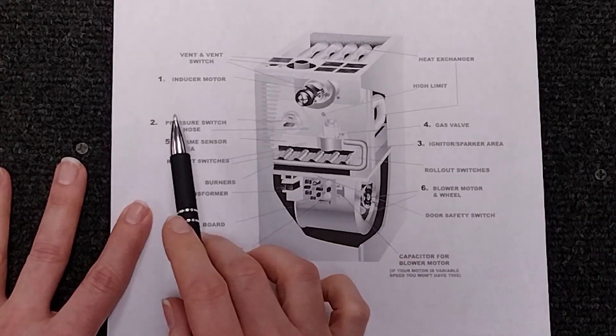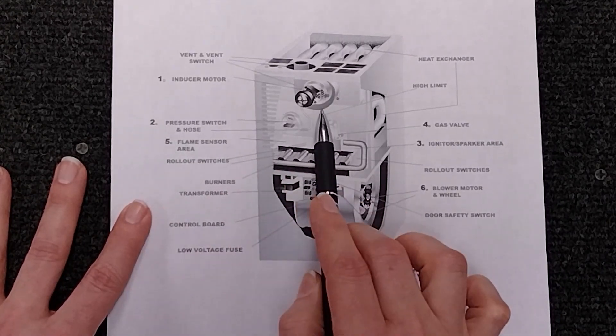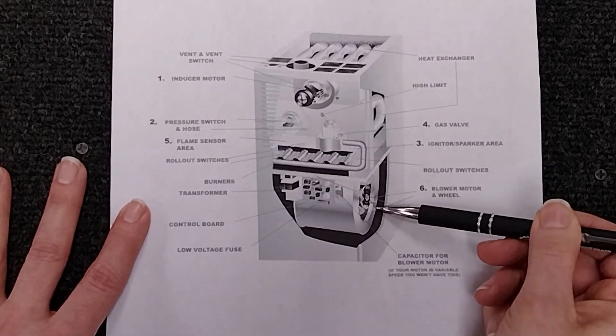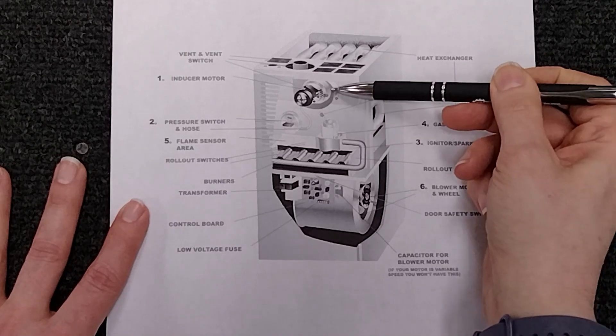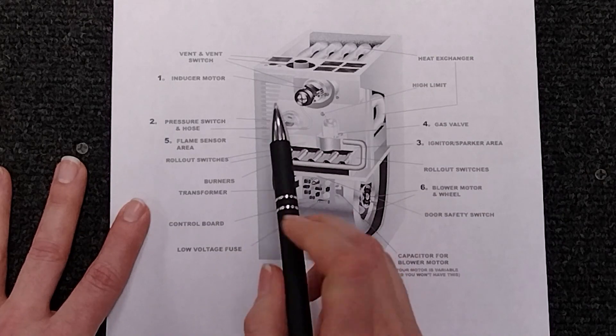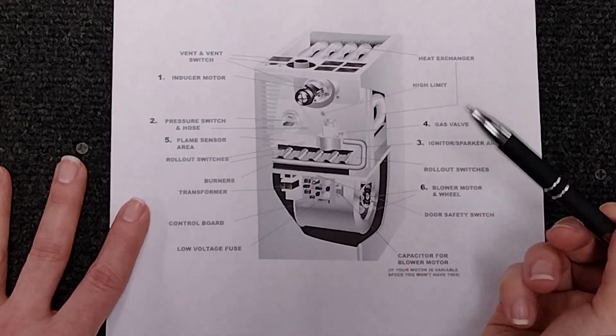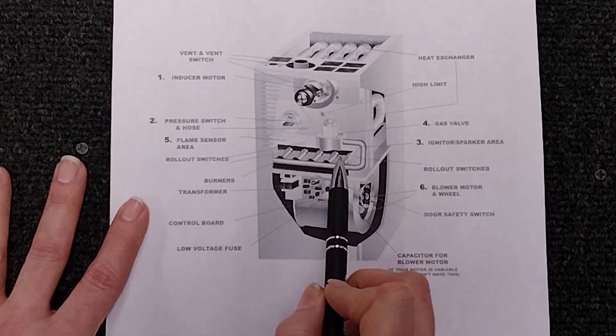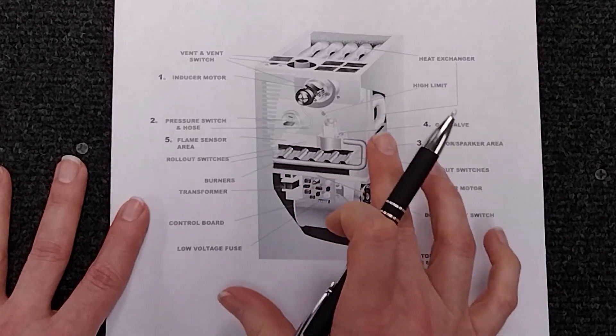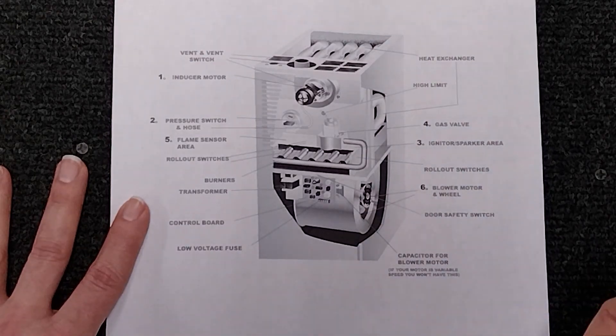So the very first thing that should happen is your vent motor or your inducer motor should come on. Your blower motor and your inducer motor should not come on at the same time. So as that inducer motor comes on obviously it's going to be a safety thing because we're dealing with gas. So noxious fumes, any sort of combustion, that needs to be vented out of your unit up through the roof.